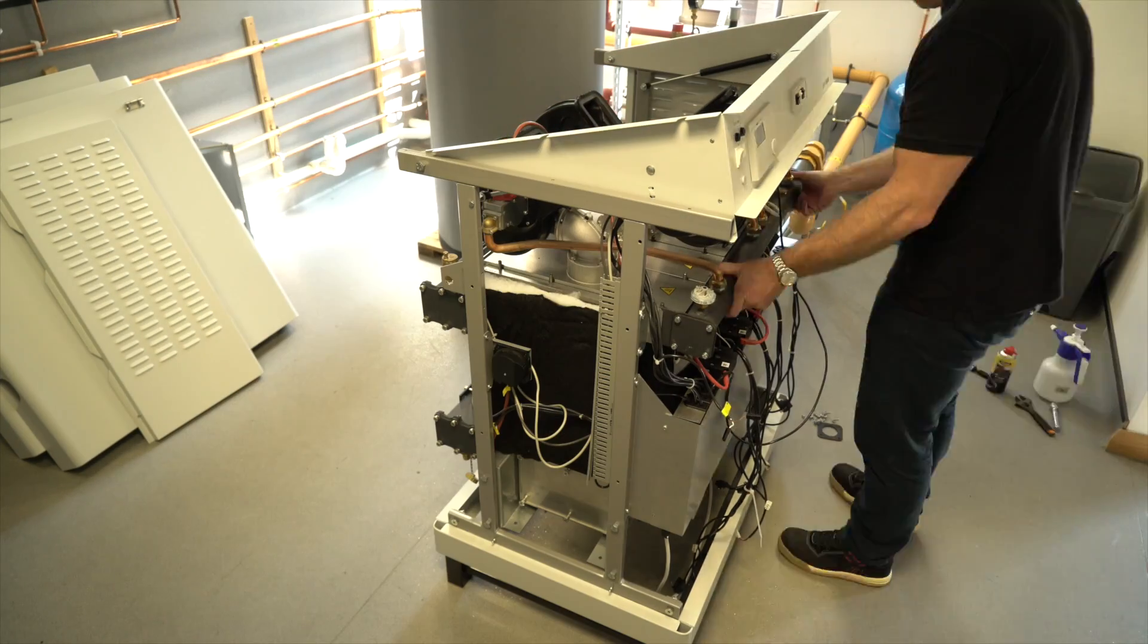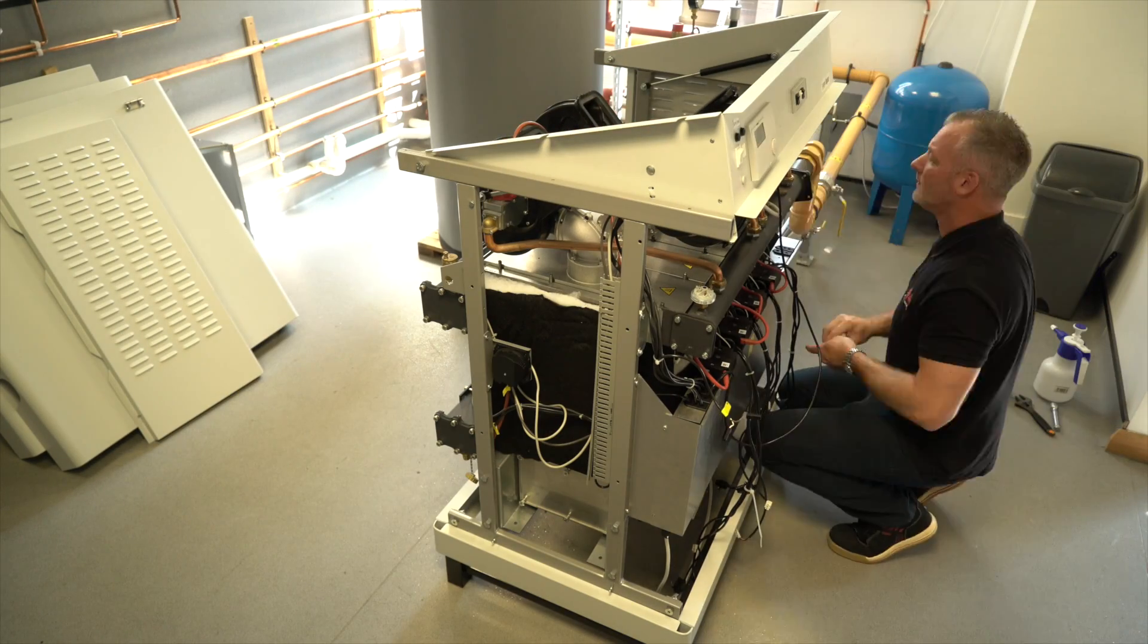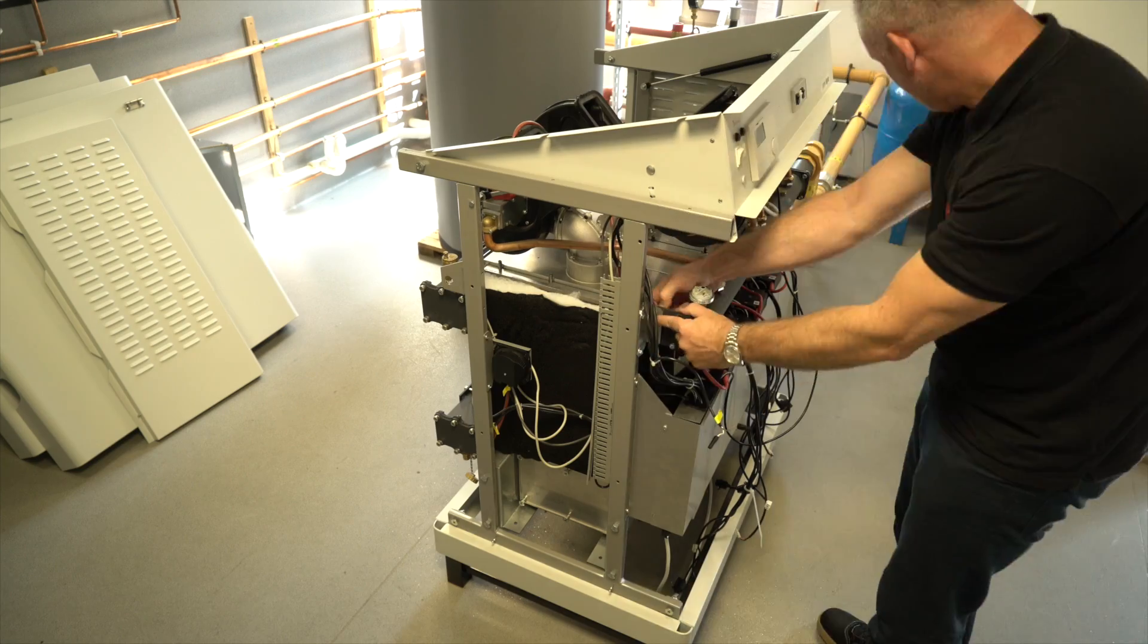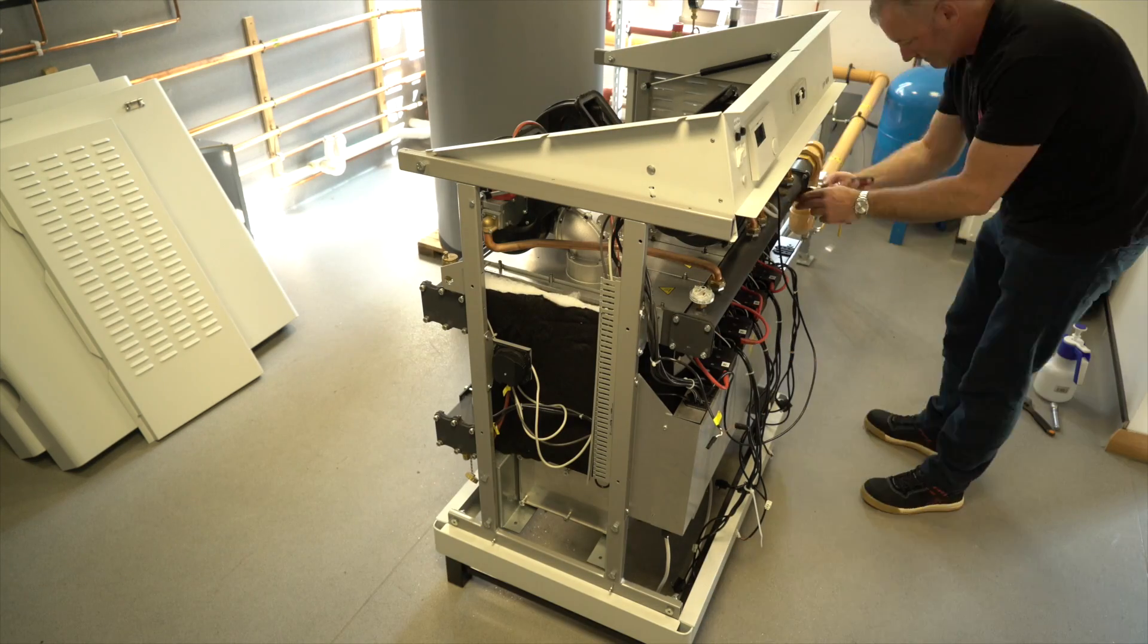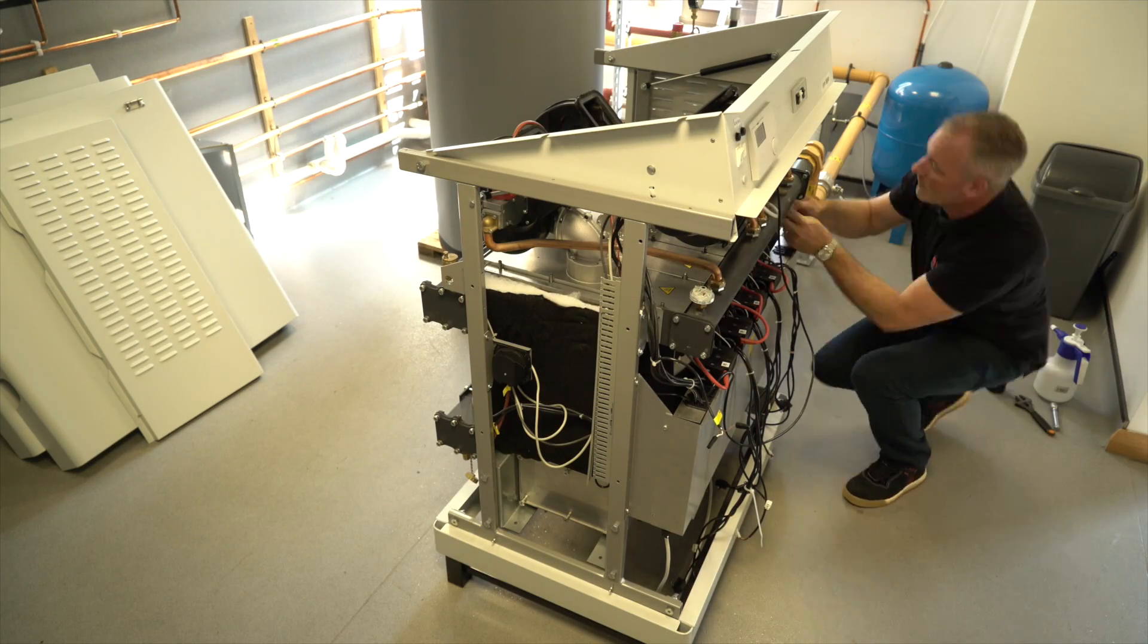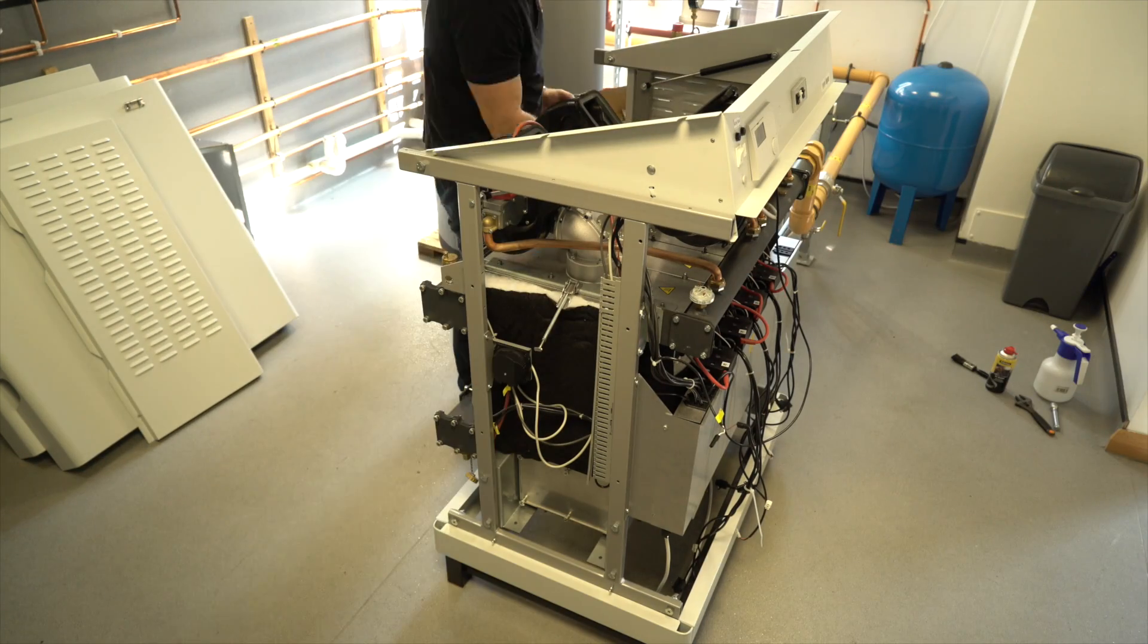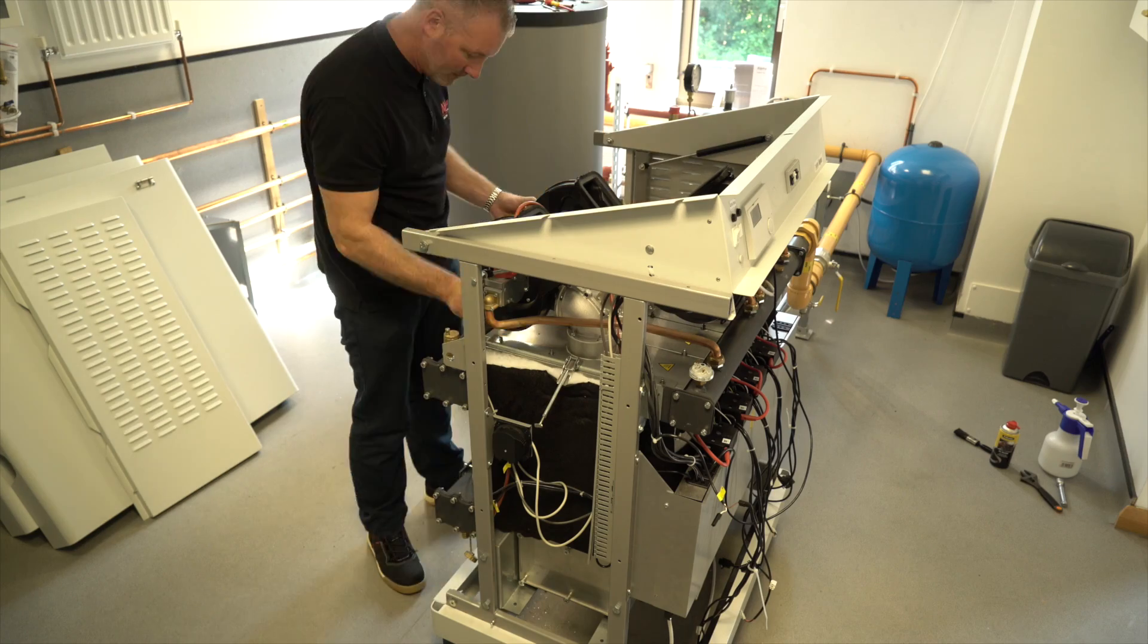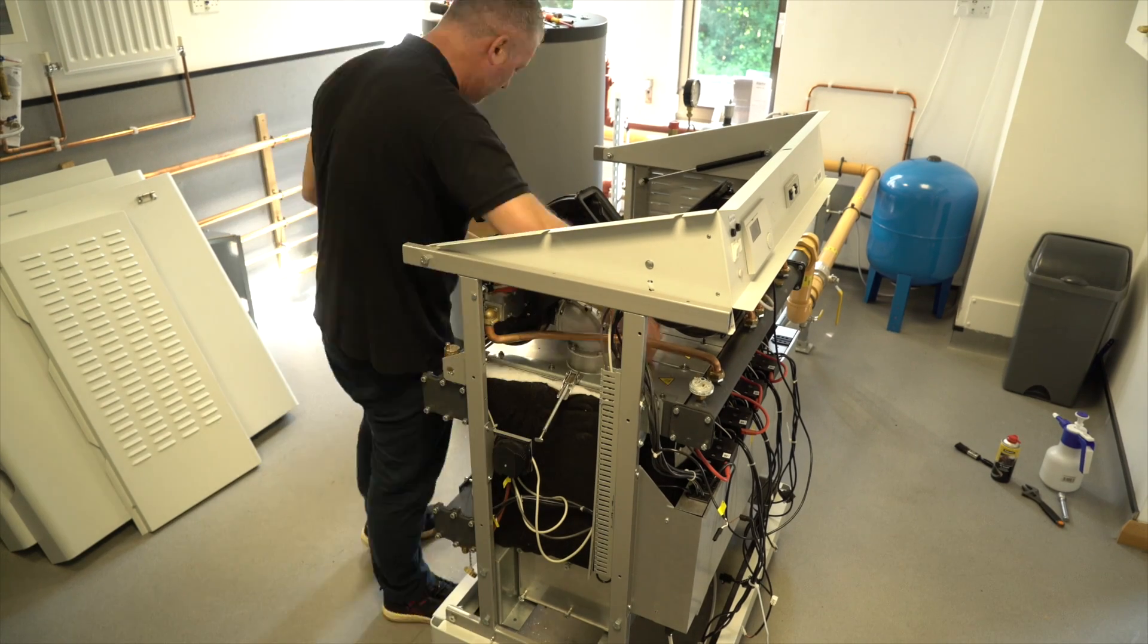Reassemble in reverse order. Lower the burner block and tighten all nuts to a torque of 13 Nm. Reconnect gas supply and carry out a tightness test on the manifold.